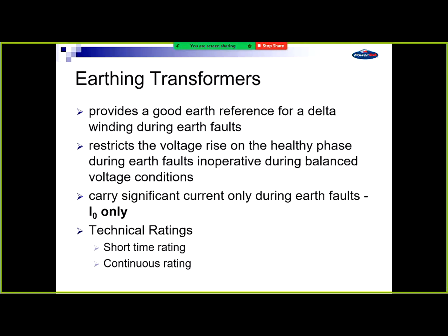So you don't get floating voltages, and you don't get overvoltages, what's called a voltage rise, on the healthy phases. But the earthing transformer will only have a zero sequence current. So it also gives an earth reference, and actually it gets used a lot in far north Queensland. We've got 132 to 22 kV. They've got a 22 kV network. We've got these 132 to 22 kV step down transformers, which are star delta, and then we have an earthing transformer. So for the 22 kV network, that's the earth reference for them, which will give them earth fault current so that they can set their protection. So it has that advantage, as it keeps the overvoltage down, and then it makes protection a lot easier.